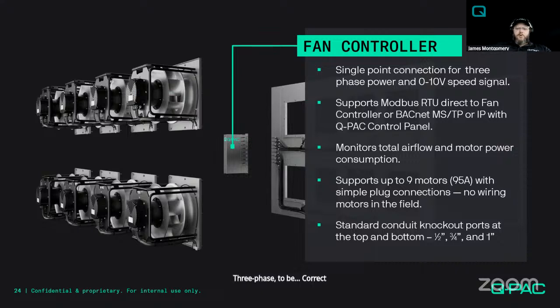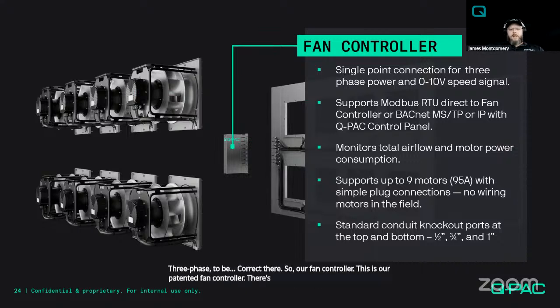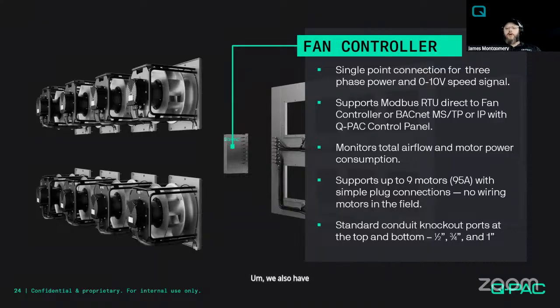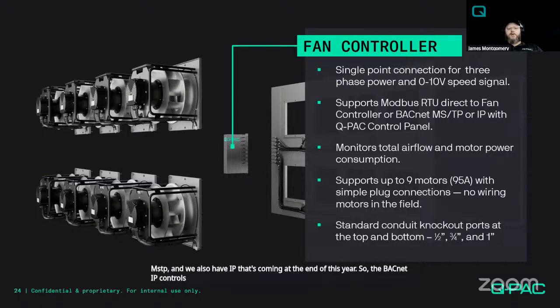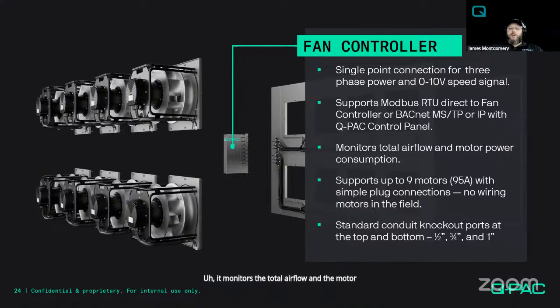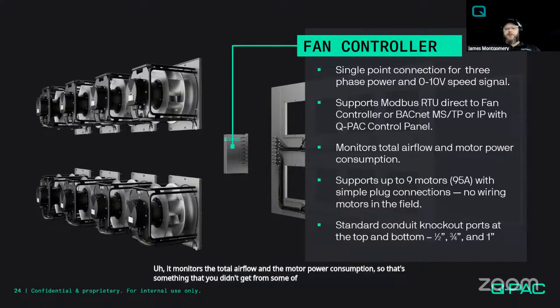So our fan controller, this is our patented fan controller. There's a single point connection. This is where your controls and electrical contractor is going to land, and that's the only place they're going to have to land. No additional wiring to all those fans like we talked about. This thing supports Modbus. We also have a fan controller that supports the BACnet MSTP, and we also have IP that's coming at the end of this year. So the BACnet IP controls that people have been asking for, that's going to be directly in this controller. It monitors the total airflow and the motor power consumption. So that's something that you didn't get from some of your basic systems. So you're going to get some monitoring, and a lot of those points are going to be over BACnet if you're interested in them. There are some analog points too. You can send an analog run signal.